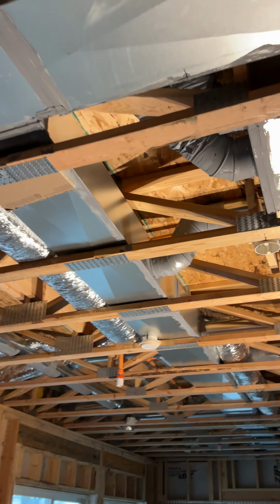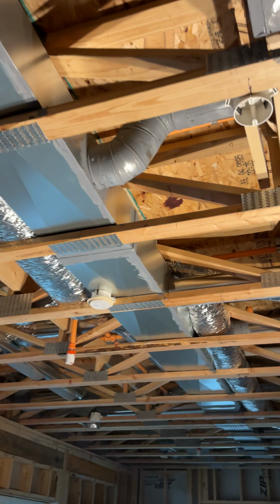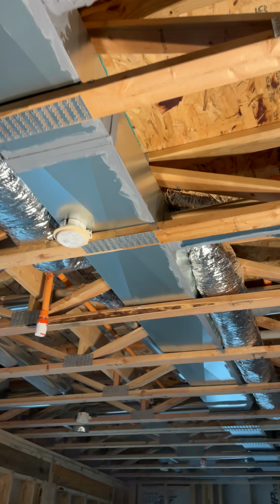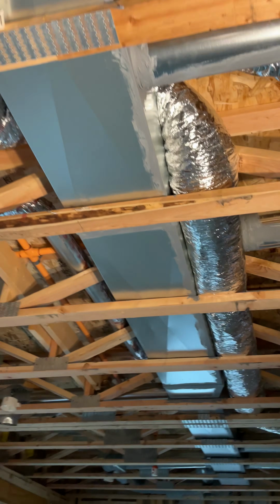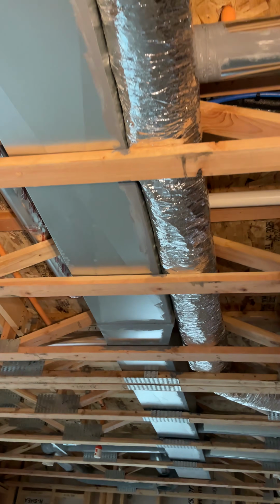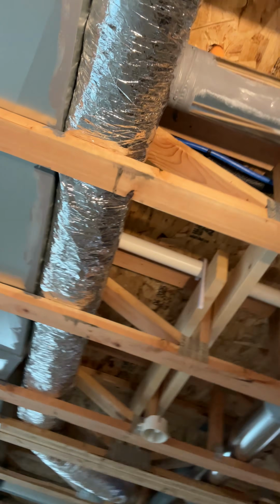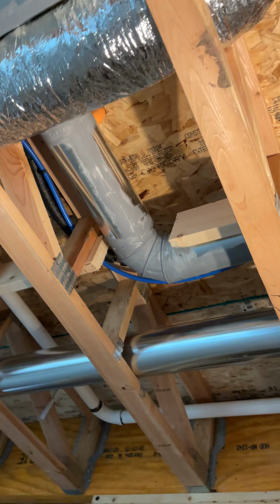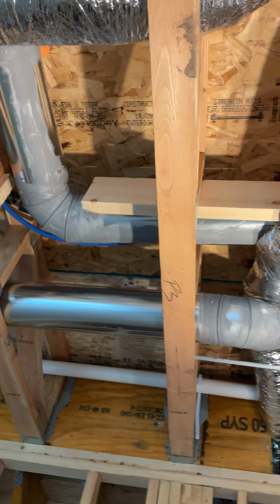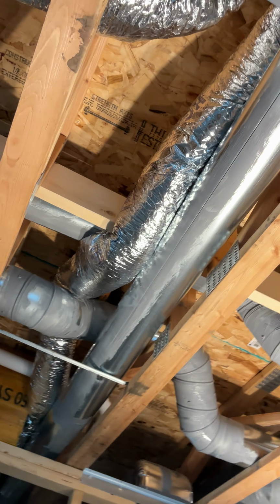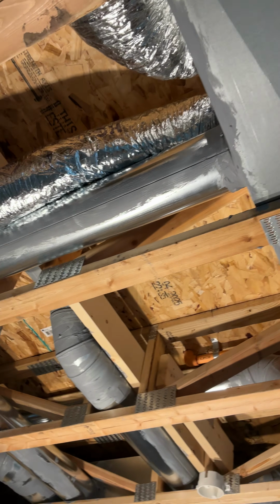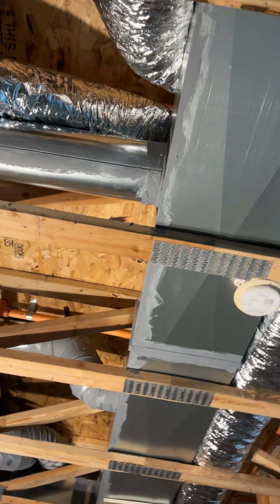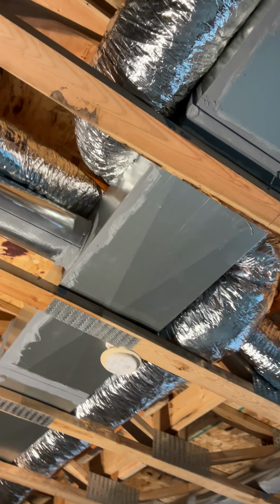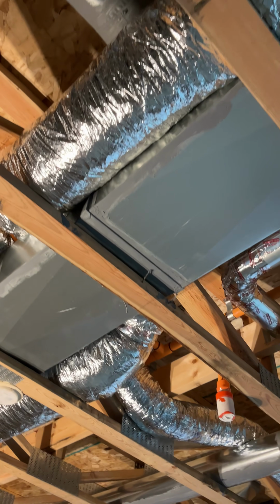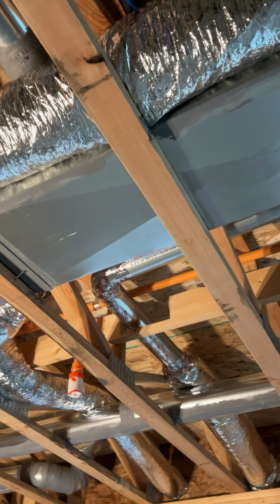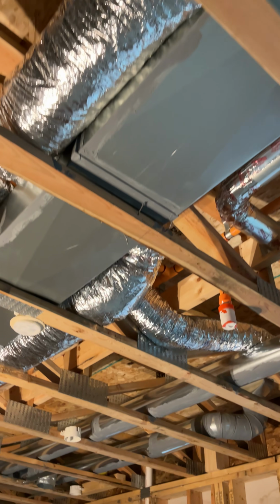One detail that is essential to getting an airtight duct system is air sealing as early as you can, while you still have access to all your ductwork. You can see here that we've got mastic painted onto all the seams and all the connections of the ductwork. We like to see our mastic painted about nickel thick and hitting any connections in boots. We also are looking for air sealing of the boots to the subfloor and any connection points. It's going to be much easier to do this now than it is after the fact.